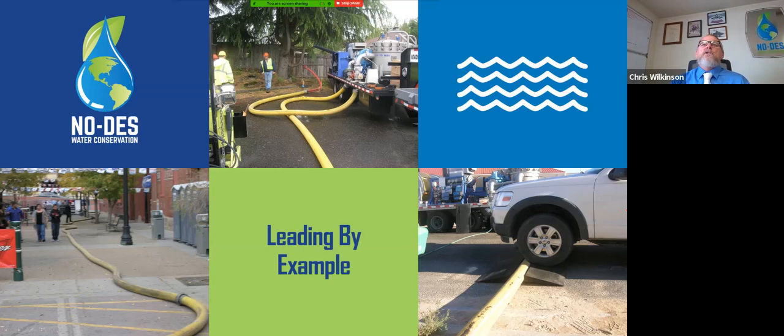Center is, this shows up in Portland, Oregon, when we're up there at Portland Water Bureau. This is a blow off here, 2 inch, that goes back a 2.5 inch fire hose, goes to 5 inch here. And then this hose on the outlet goes all the way back down to the hydrant at the end of the street. So we can achieve up to about 600 gallons per minute to do those smaller mains on the cul-de-sac dead ends. And this was a mainstay for them.